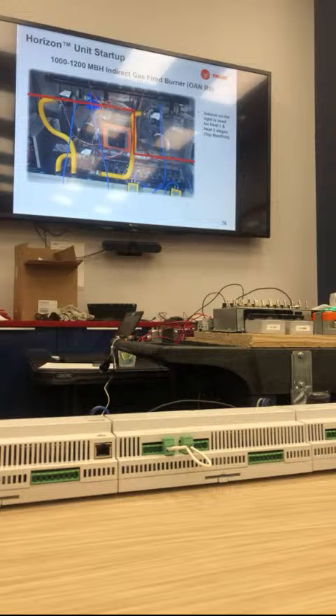They burn at 75,000 BTUs per tube instead of the 25,000 BTUs per tube. So these are monster heaters that are going in there. They're very long. These tubes are 110 inches long.